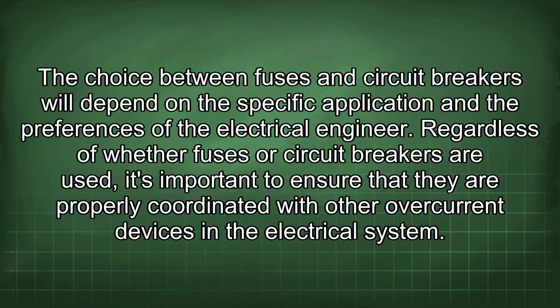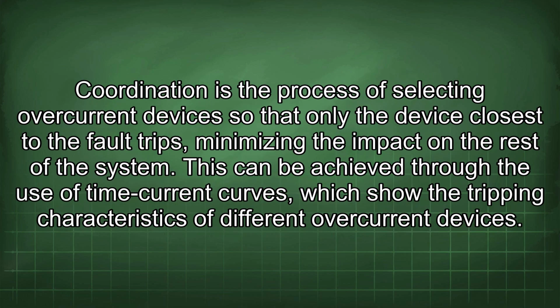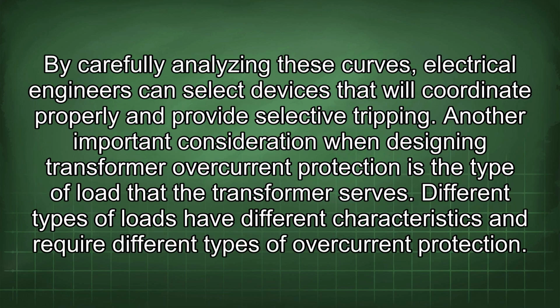Regardless of whether fuses or circuit breakers are used, it's important to ensure that they are properly coordinated with other overcurrent devices in the electrical system. Coordination is the process of selecting overcurrent devices so that only the device closest to the fault trips, minimizing the impact on the rest of the system. This can be achieved through the use of time current curves, which show the tripping characteristics of different overcurrent devices. By carefully analyzing these curves, electrical engineers can select devices that will coordinate properly and provide selective tripping.